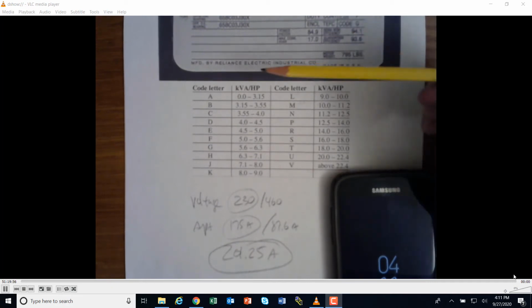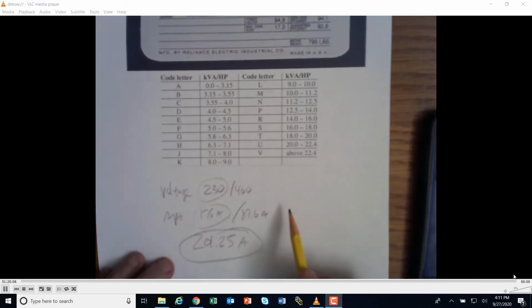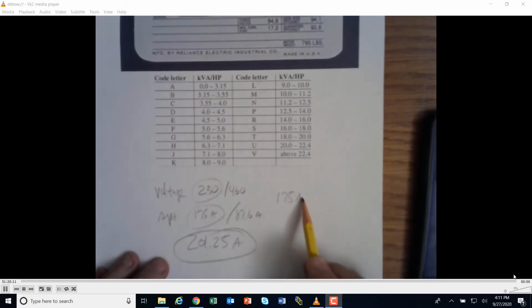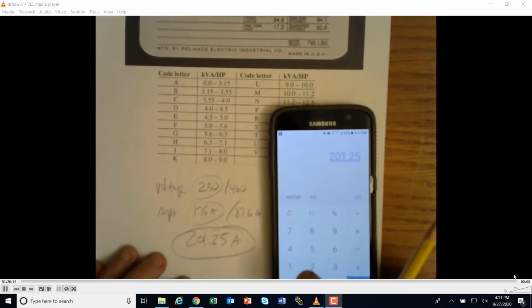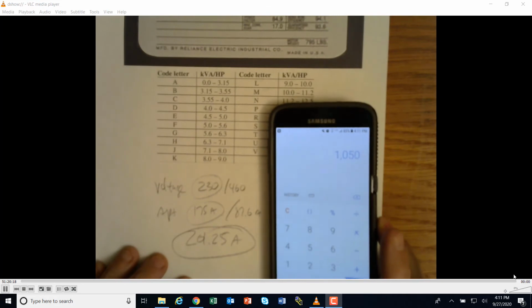It's a motor code G. So if we look at our kVA per horsepower, it looks like it's a locked rotor amps of somewhere between 5.6 and 6.3. So, you know, roughly 6 on a locked rotor amp. So we were taking a look at this 175 amps right here, and we multiplied by 6. You're going to get a pretty big number right here. 175 times 6, you're going to get over 1,000 amps.